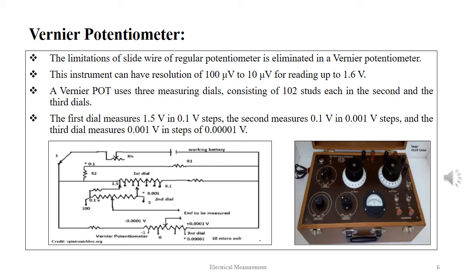The Vernier potentiometer is a special arrangement by which we can enhance the resolution of a DC potentiometer. The instrument can have a resolution as low as 10 microvolts for readings up to 1.6 volts.